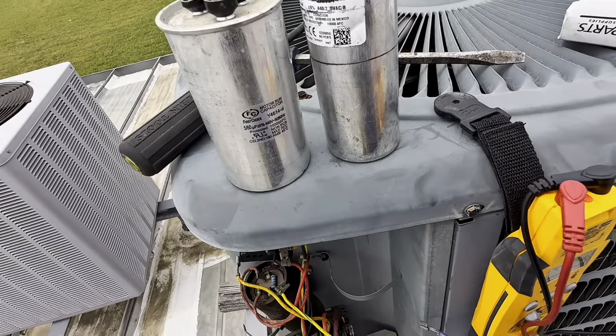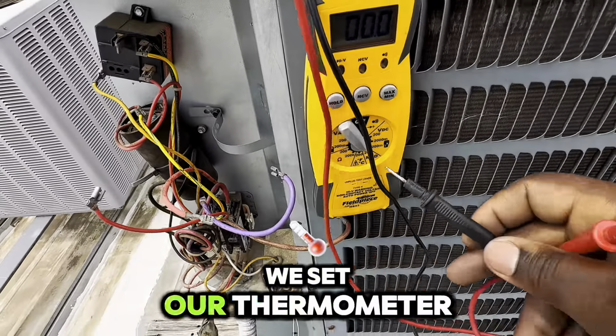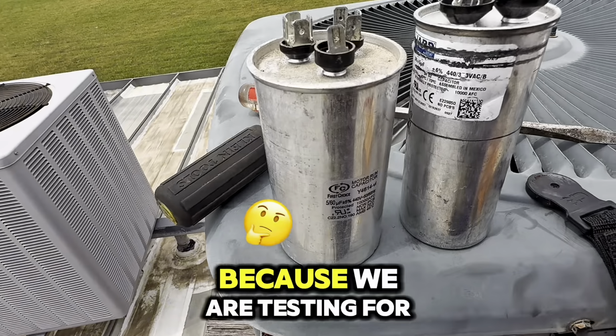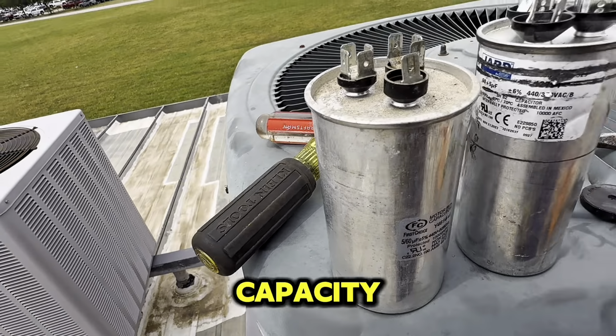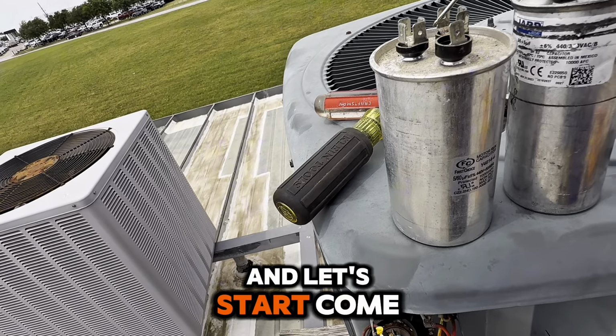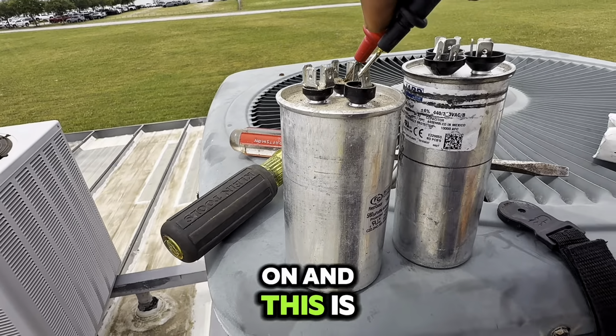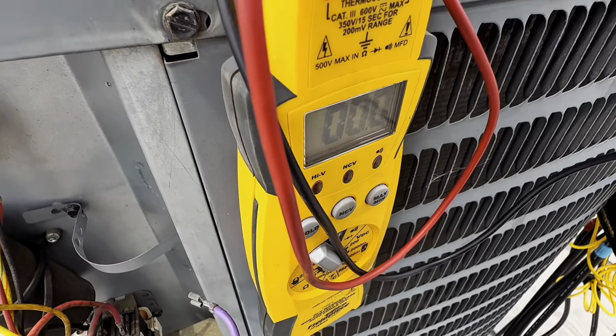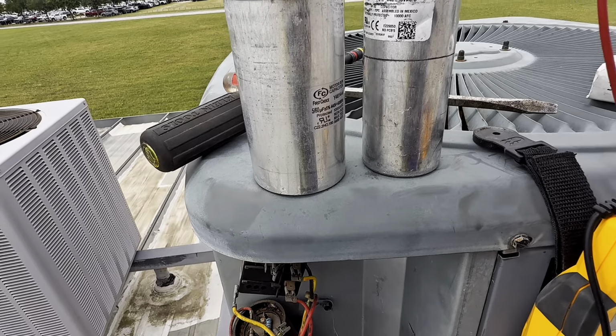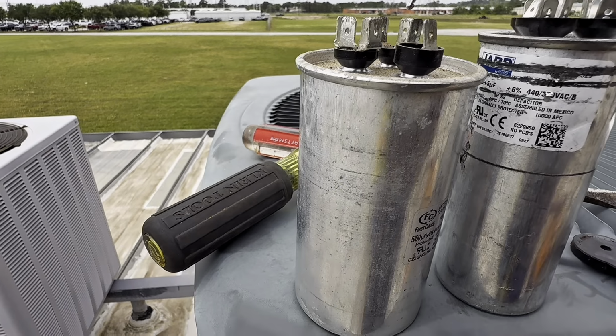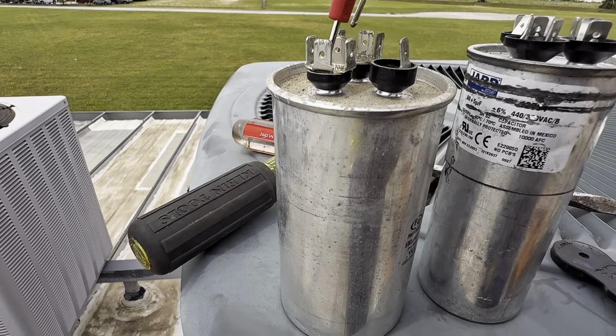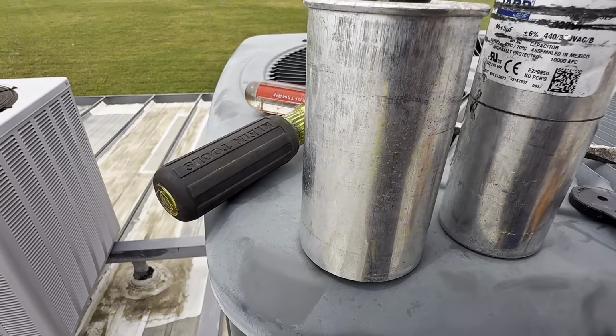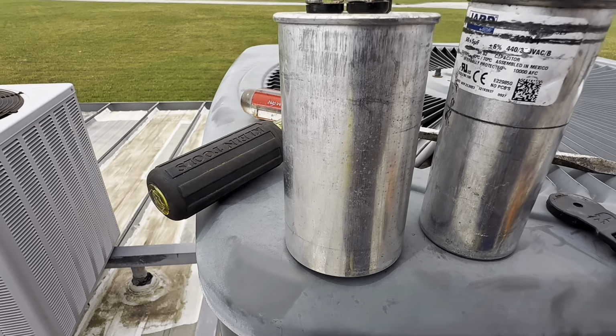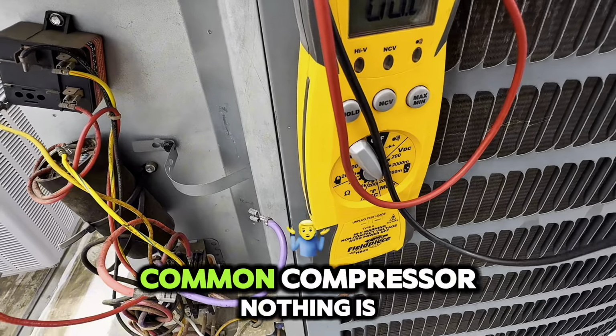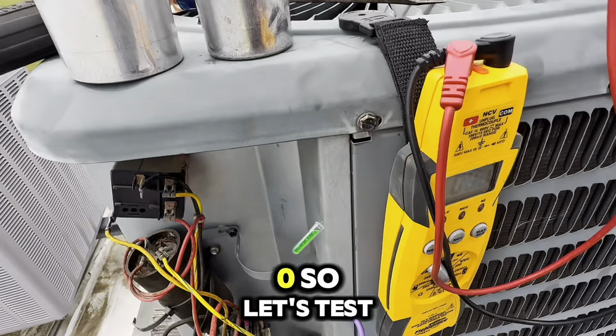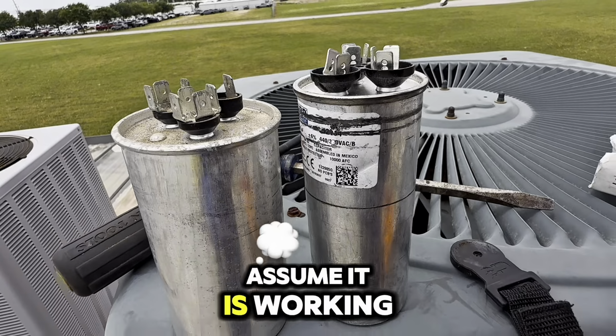So we set our multimeter to MFD, that's microfarad, because we are testing for the capacitance. And let's start with the common, and this is reading nothing. That's the common and the fan terminal. Okay, so let's use the common and the compressor. Common and compressor, nothing is reading. It reads 0, 0.